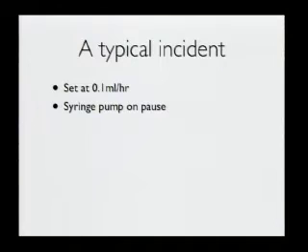And possibly a sensible design, after a couple of minutes it starts beeping, beep, beep, beep, because it has been told to deliver a certain amount of drug and it is on hold. And the designers thought possibly the nurses got distracted and they've forgotten to press the go button.